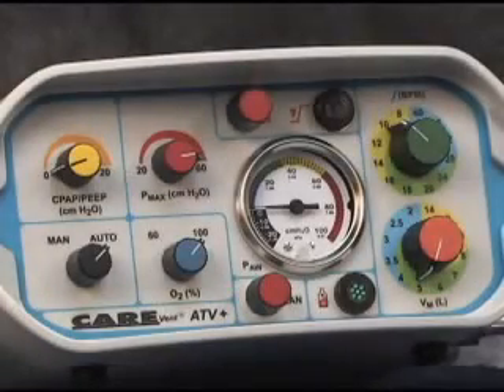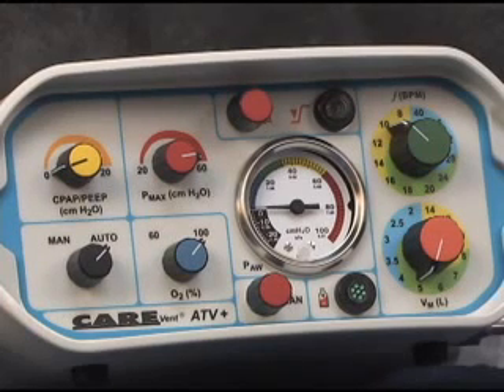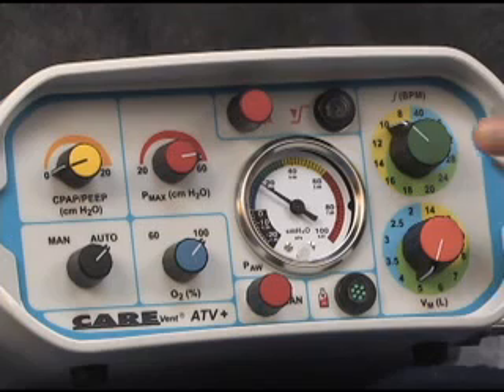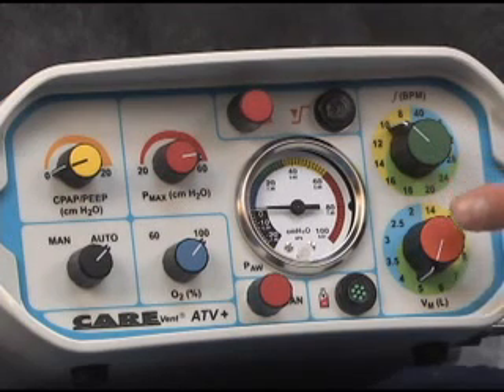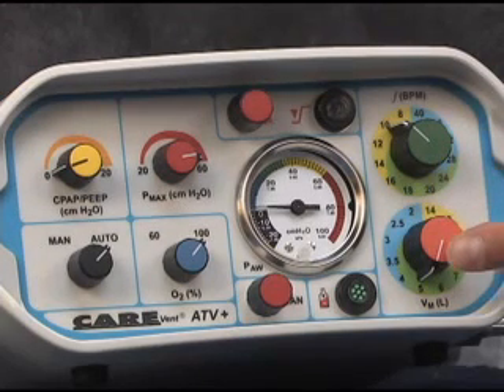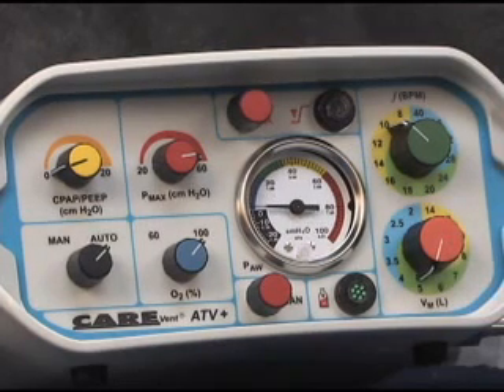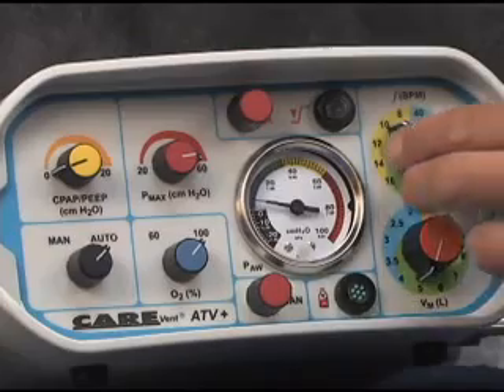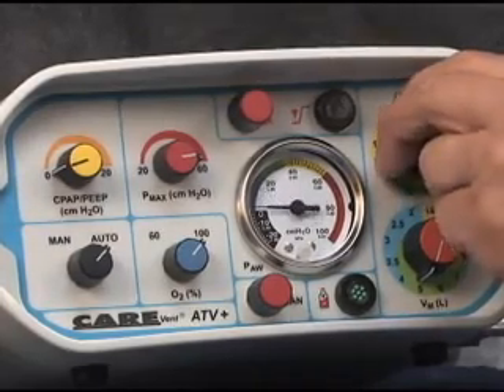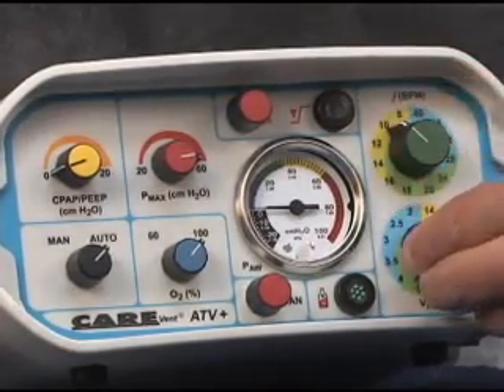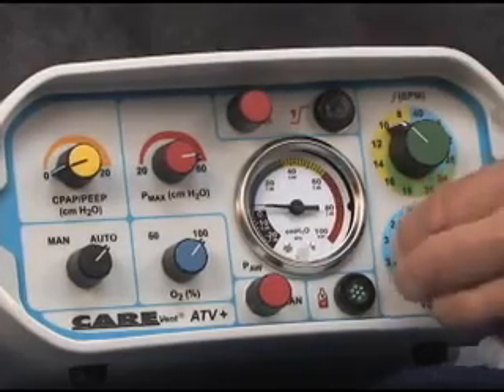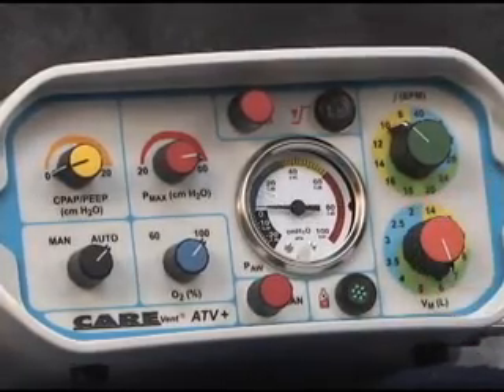The CAREvent ATV Plus and MRI are equipped with a number of controls to allow the operator to tailor the ventilation parameters to the individual patient's needs. The frequency of ventilation and minute volume delivery can be independently selected by rotating the two controls located on the right of the front panel in a clockwise direction from low to high settings. Each control provides 12 positions, allowing a total combination of 144 possible patient setting selections.